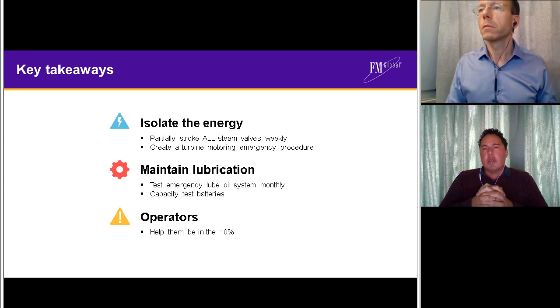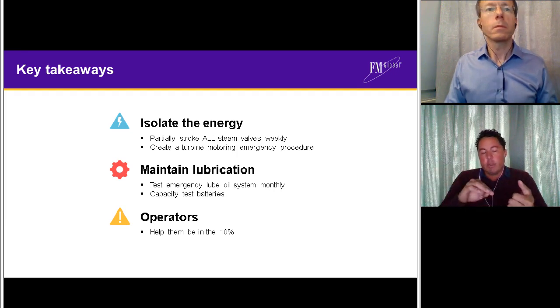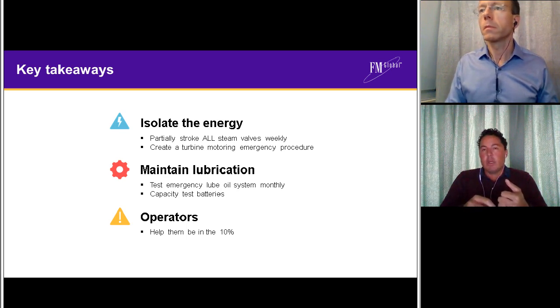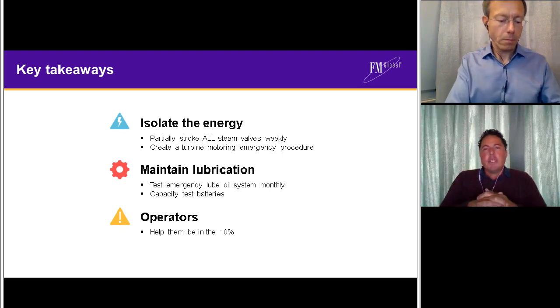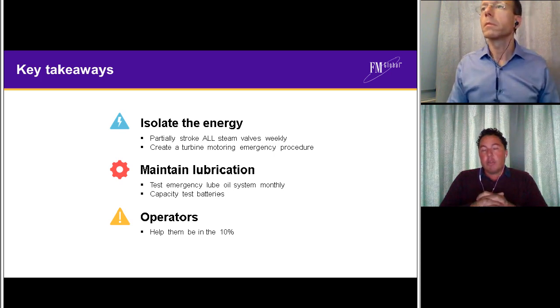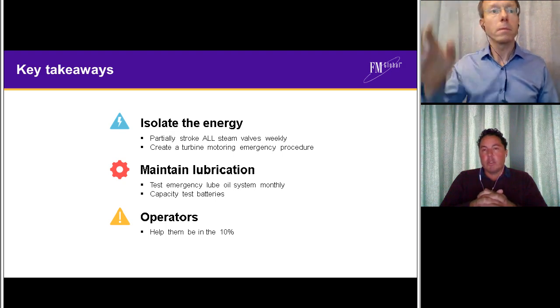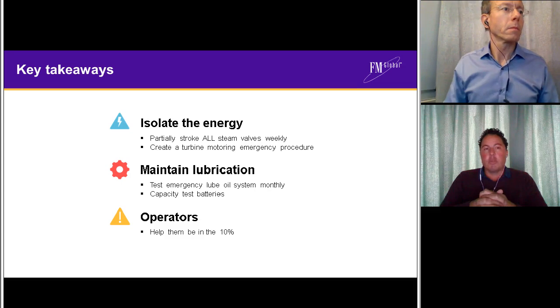There's still some work to be done, right? There's still some opportunities to improve the resilience. And some of the things I've already touched on, for instance, on the DC system supplying that emergency lube oil pump motor, what is the protection philosophy on there? Do we have trips that shouldn't necessarily be trips? For instance, a thermal overload on the pump motor. I've yet to hear a cogent argument why there should be thermal overload on those motors. If your emergency lube oil system is operating, you would surely want it to keep operating for as long as it possibly could to ensure your turbine runs down with as much lubrication as possible.